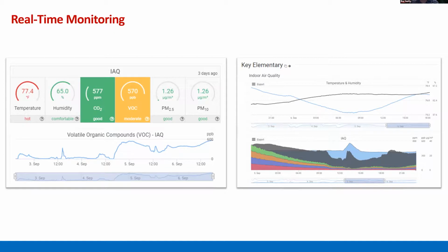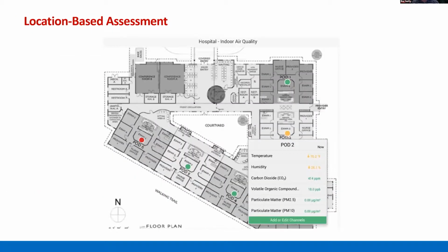The VOCs has been a really interesting one. So what we're seeing is when customers start to sanitize and also fog the rooms, the VOCs are spiking. And it's for a short time as the HVAC starts to clear that out. So the way that our customers are using that VOC monitor is basically proving to the occupants that the room was sanitized the night before or between classes. So again, we are at a point where we have to prove we are going to be held accountable.